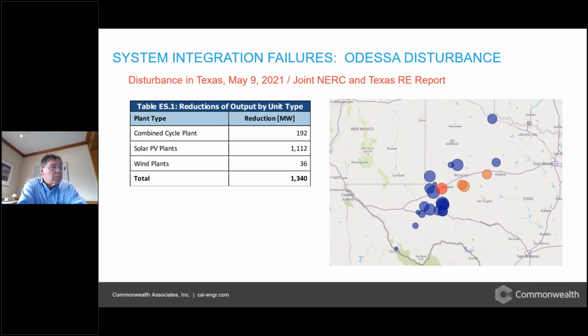So the reasons for the loss of the inverters include phase lock loop, loss of synchronism, inverter AC overvoltage and/or feeder AC overvoltage. We already discussed momentary cessation. That's another; despite all the previous incidents that came out of California, you still had momentary cessation occurring in Texas. And then also inverter under frequency and/or feeder under frequency.